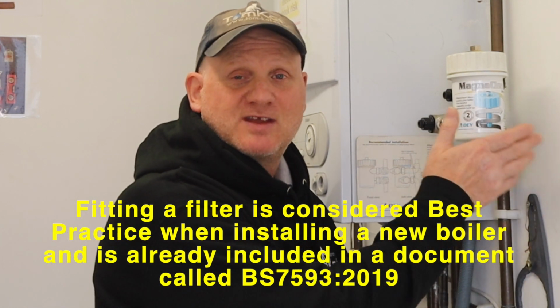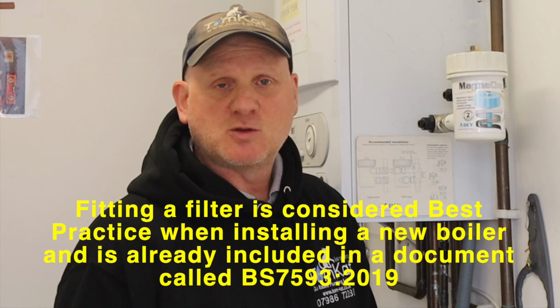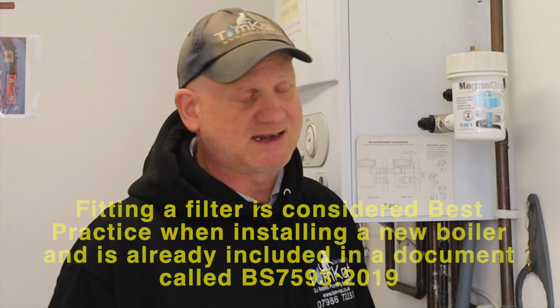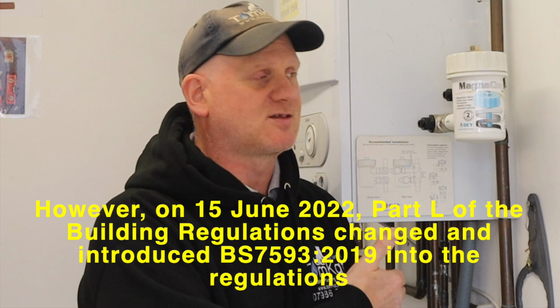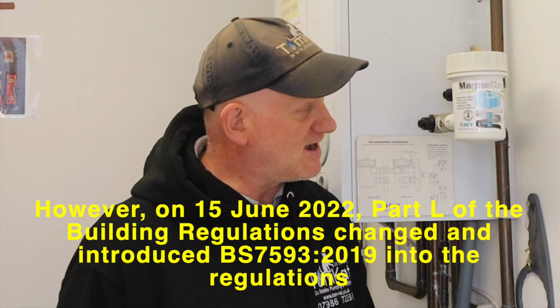So besides servicing, what else do we need to do? Now that leads me into the next one. Magnetic filters. Now, all new boilers now should be fitted with magnetic filters to protect the boiler from sludge and magnetite corrosion from the heating system, to keep it nice and clean inside, because a dirty boiler is an inefficient boiler. So these will help you keep your boiler efficient and keep it going for longer, because if your boiler is full of sludge, it's not going to last very long.